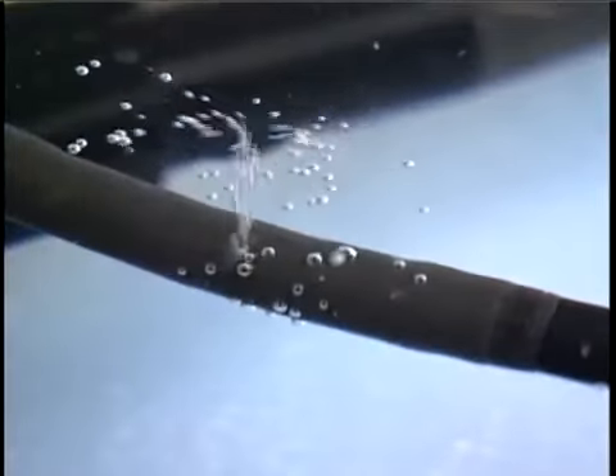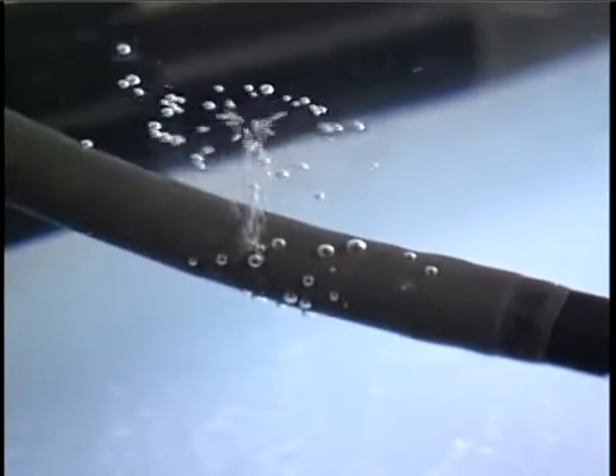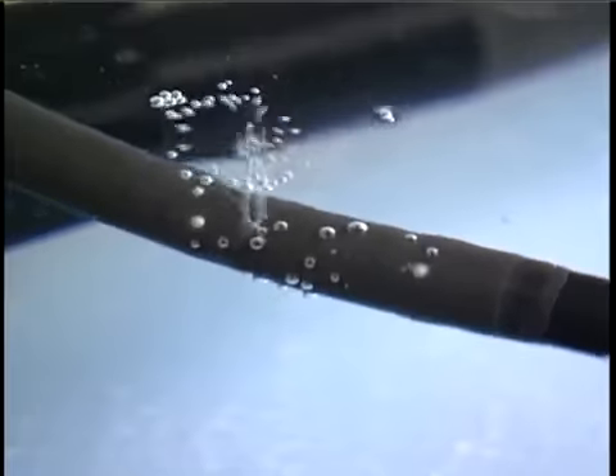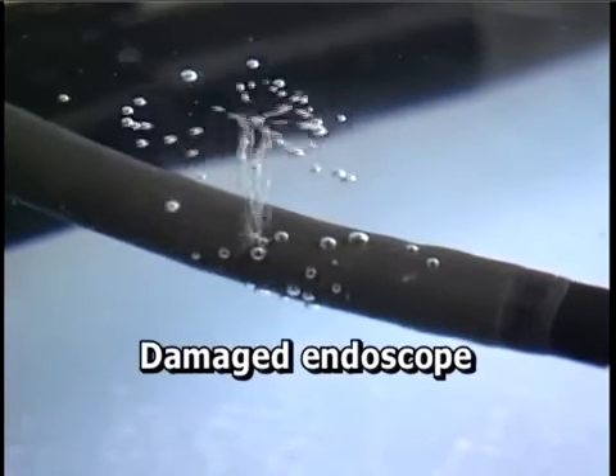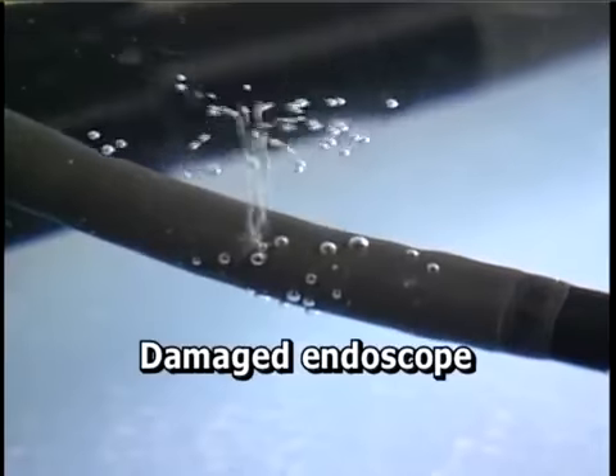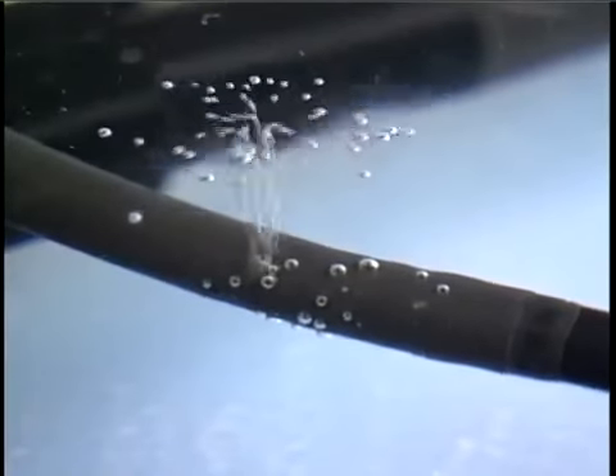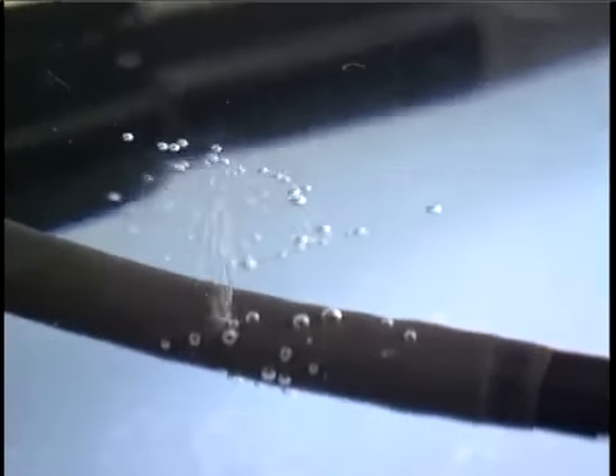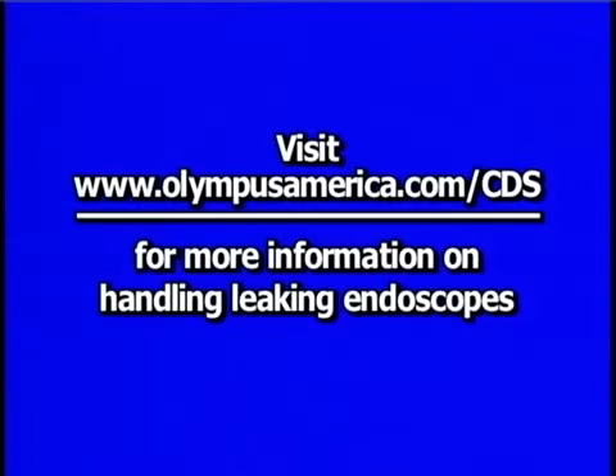In contrast, if you do observe a continuous stream of bubbles, the endoscope is leaking. Leaks like this will allow fluids to penetrate and damage the endoscope. If you observe such a leak, do not turn the air supply off. Rather, remove the endoscope from the water, blow out the channels with air, and dry the endoscope prior to turning off the leakage tester. Contact Olympus for instructions on how to reprocess a leaking endoscope prior to sending the endoscope to Olympus for repair.